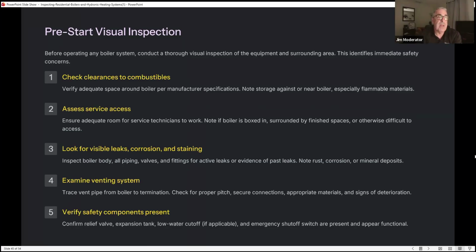Before operating any boiler, we want to do the following. We want to check clearances to combustibles, assess service access, look for visible leaks, corrosion, and staining, examine venting systems, and verify the safety components are present. We want to make sure there's adequate space around the boiler and room for technicians to work. Again, on all these things, we want to look for leaks, corrosion, and staining, examine the venting system, and confirm the relief valve, expansion tank, etc.